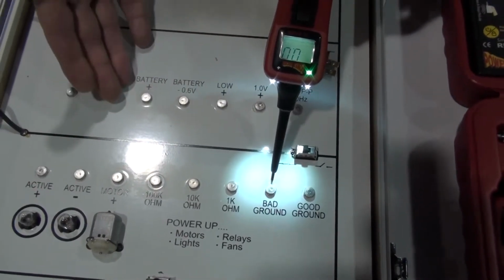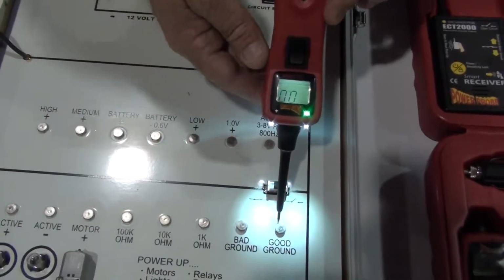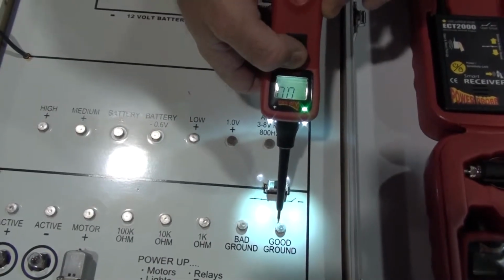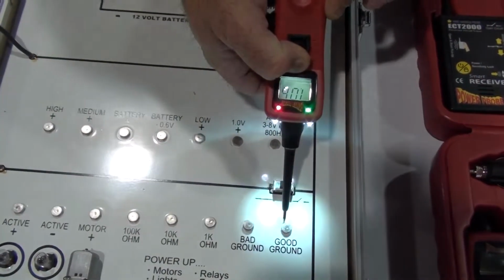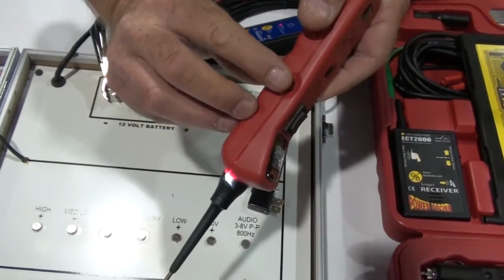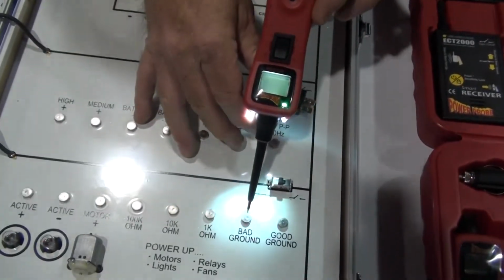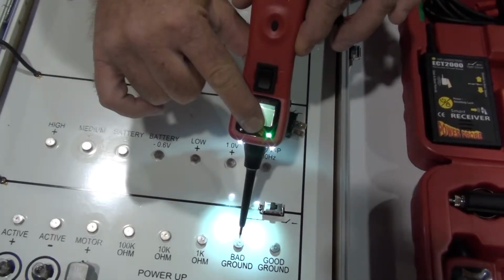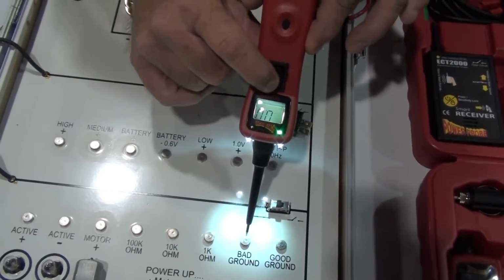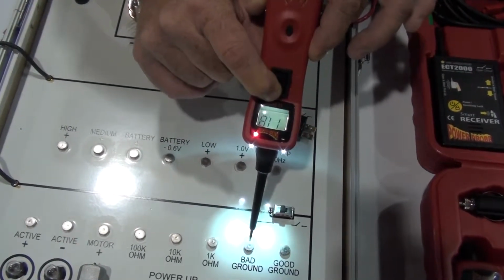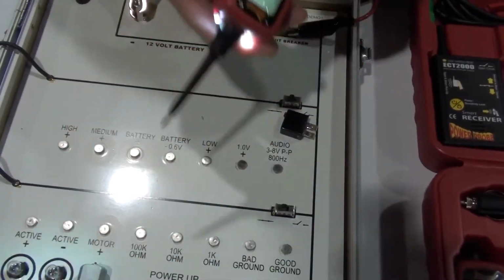To verify it being a good ground or a bad ground, watch this. You press the rocker switch forward, and we're going to short it out. It just tripped my circuit breaker. That verifies that I have a good ground there. Press the reset button, watch this. Contact the tip, I'm getting a green indicator, we're going to try to short it out. It doesn't trip the circuit breaker. That is a bad ground without a voltage drop test. It took you a second to find it.